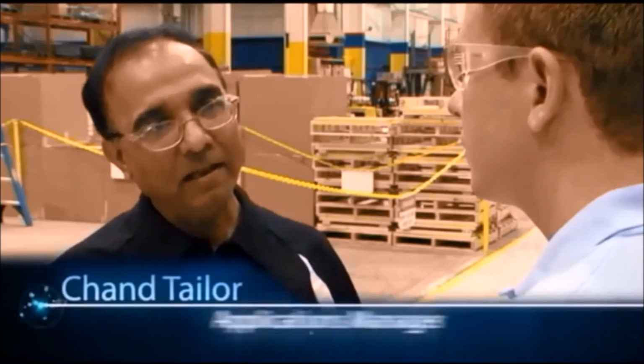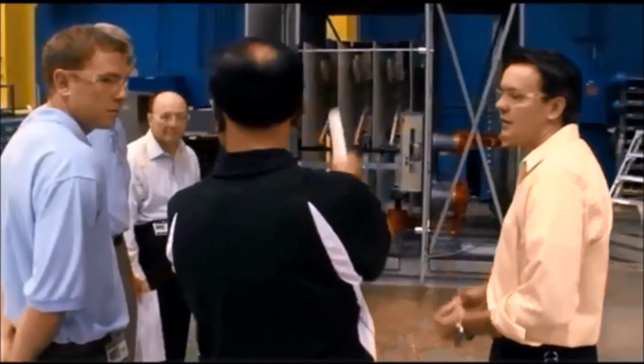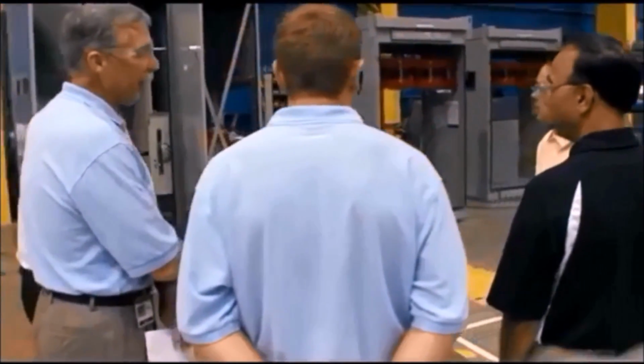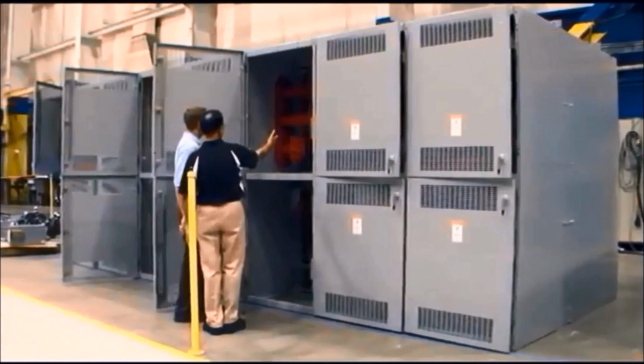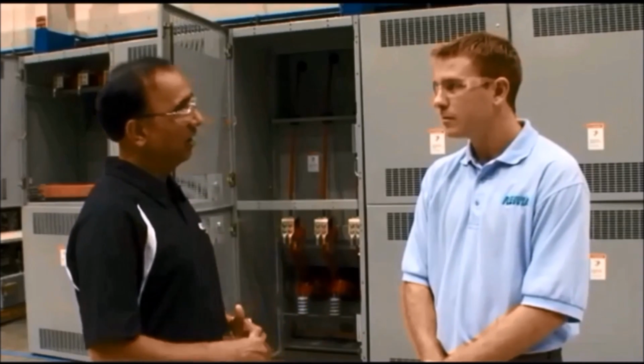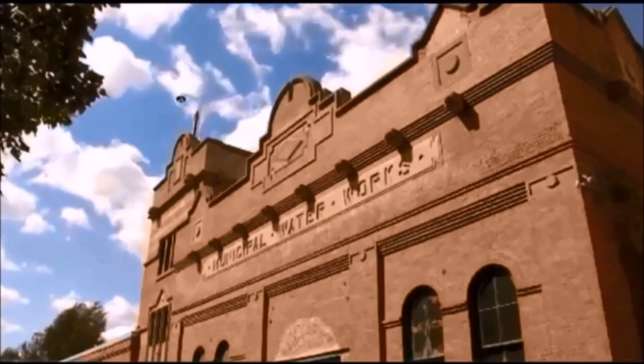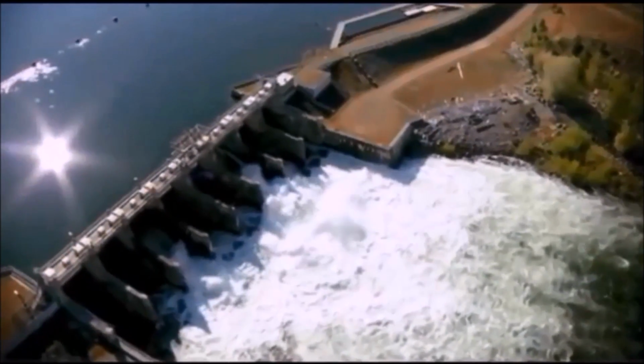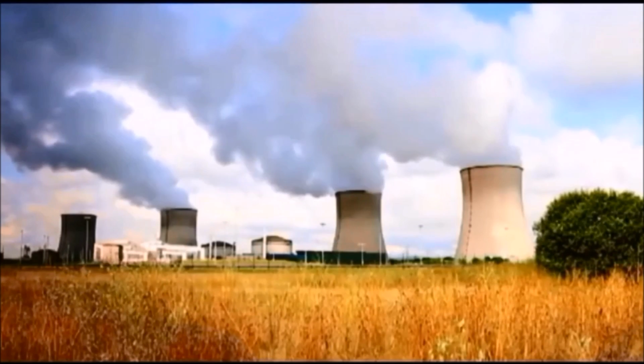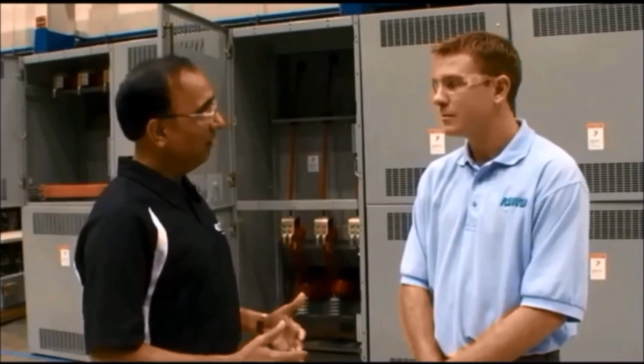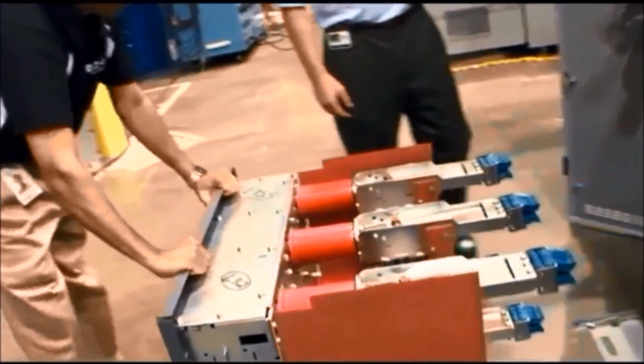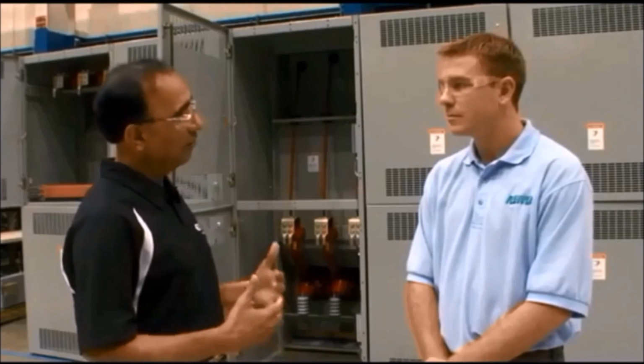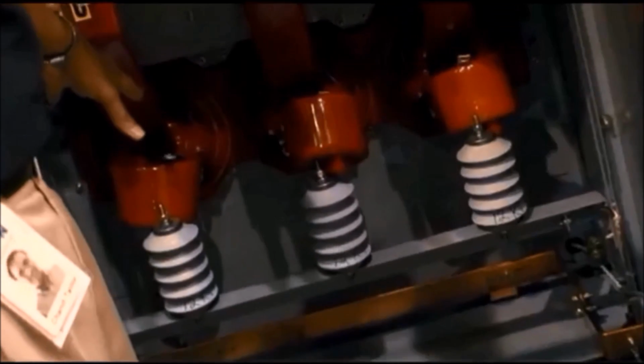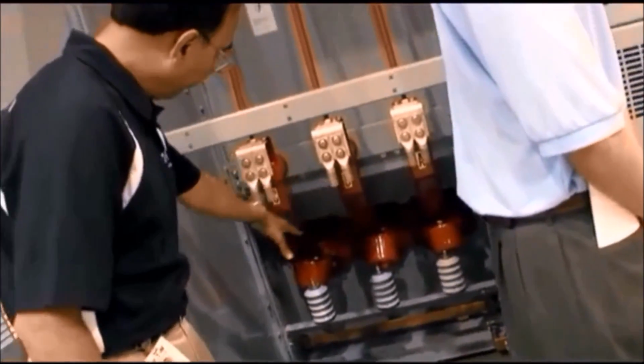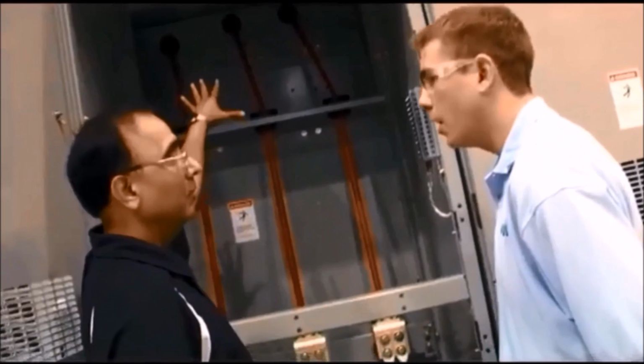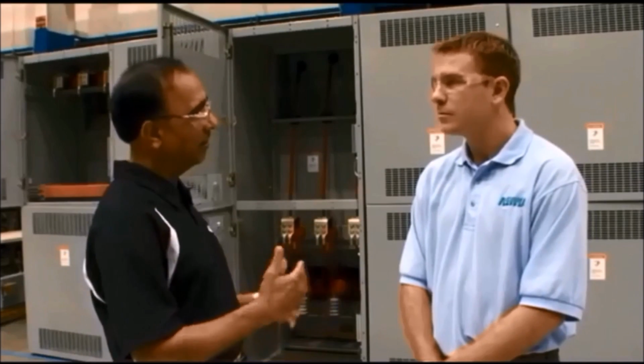Switchgear is basically similar to a panel board, except it's a large switchboard designed to handle very high voltage and high currents. It's used in large industrial facilities, in wastewater treatment plants to control large motors, and in power generating stations to turn on and off many loads. It consists of switching devices such as circuit breakers or switches, measuring devices such as current and voltage transformers, protection and control devices such as relays, and conductors such as buses and connections to carry power from point A to point B.